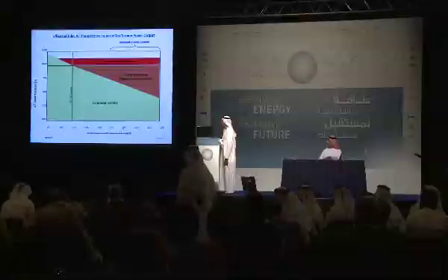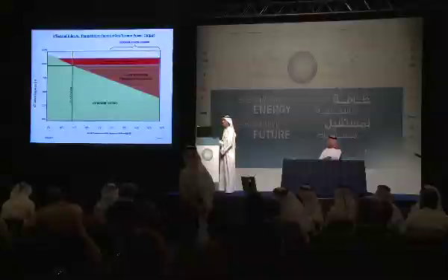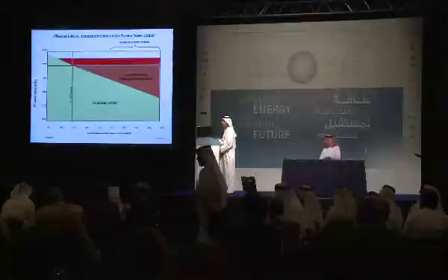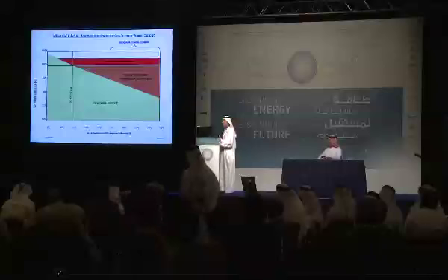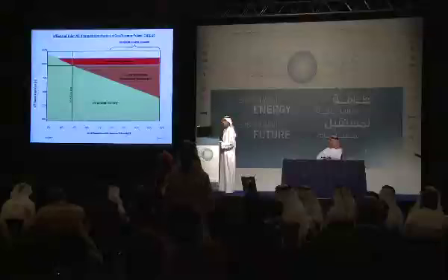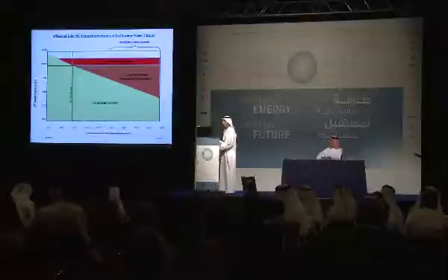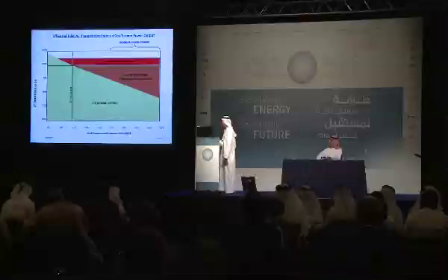Air in the summer is less dense, compressors are less efficient, the volume of air for combustion is less, and output is less. Normally, for each 1 degree temperature, for the F class, the big units, around 1.8 megawatt reduction, for the E class around 0.9 for each degree ambient increase.